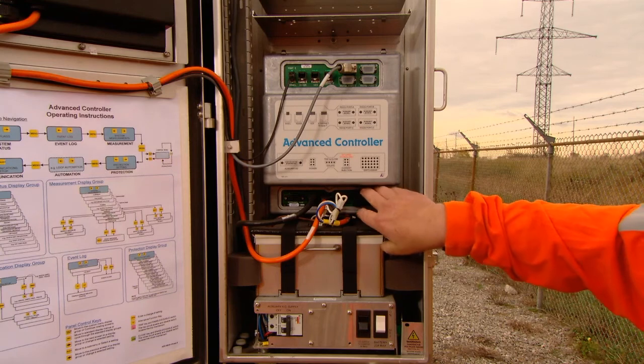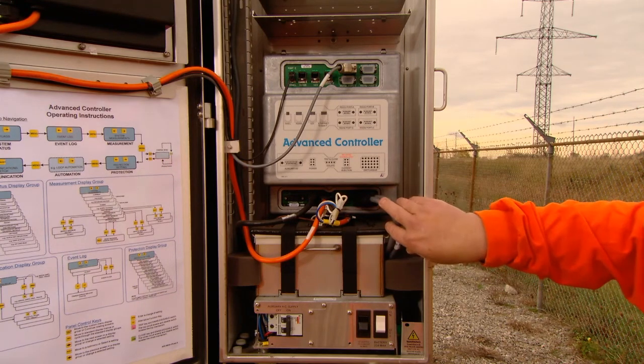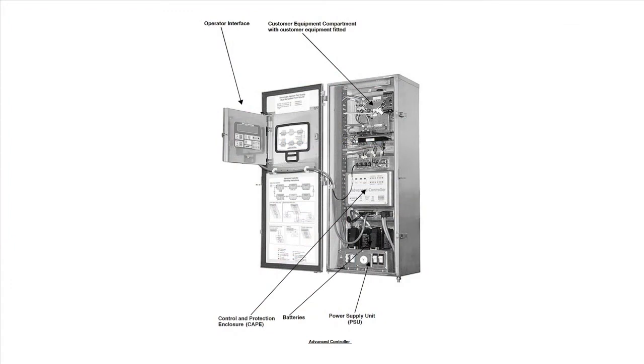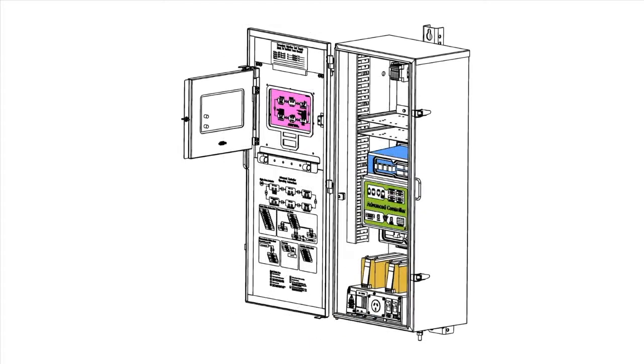The controller interface is accessed on the outside of the panel door. The ADVC controller reads and displays the information stored in its attached switchgear. It also trips and closes the switchgear for the primary purpose of protection. The ADVC consists of an electronic switchgear controller known as the Control and Protection Enclosure, or CAPE, that monitors the switchgear and provides protection and communications functions, an operator interface mounted on the Control and Protection Enclosure inside the cubicle, and a power supply which also supplies power for customer equipment.